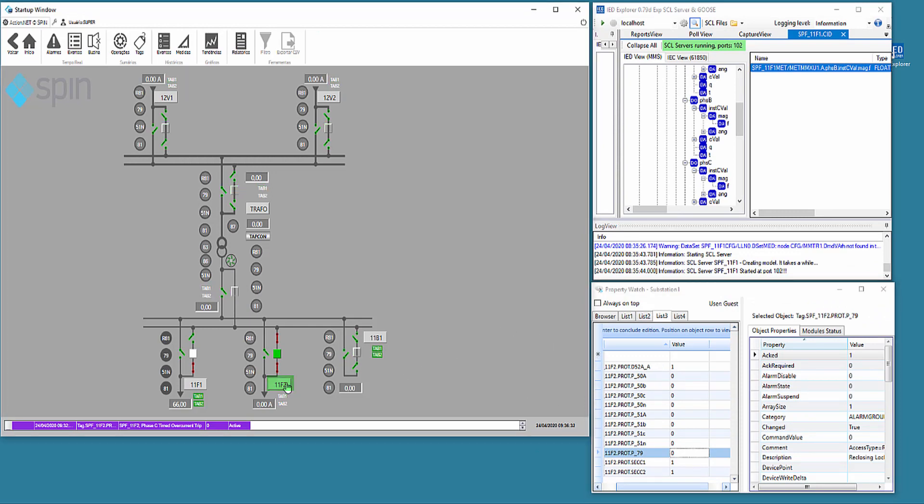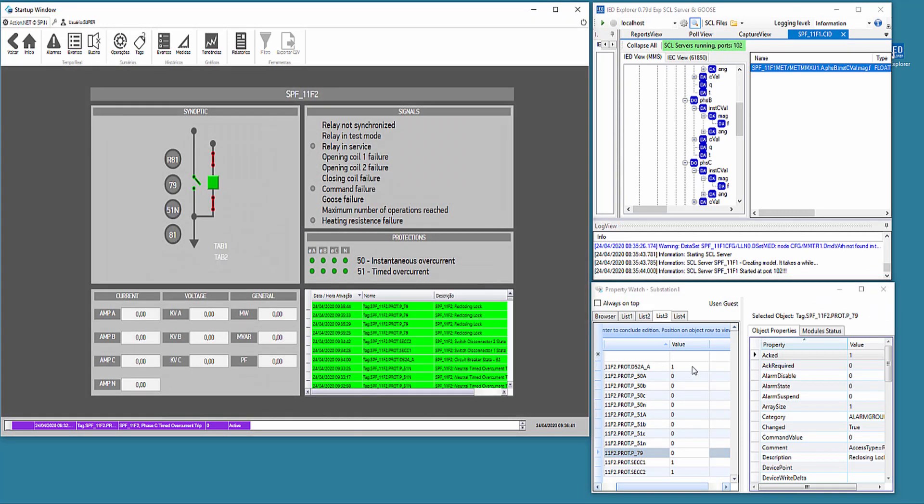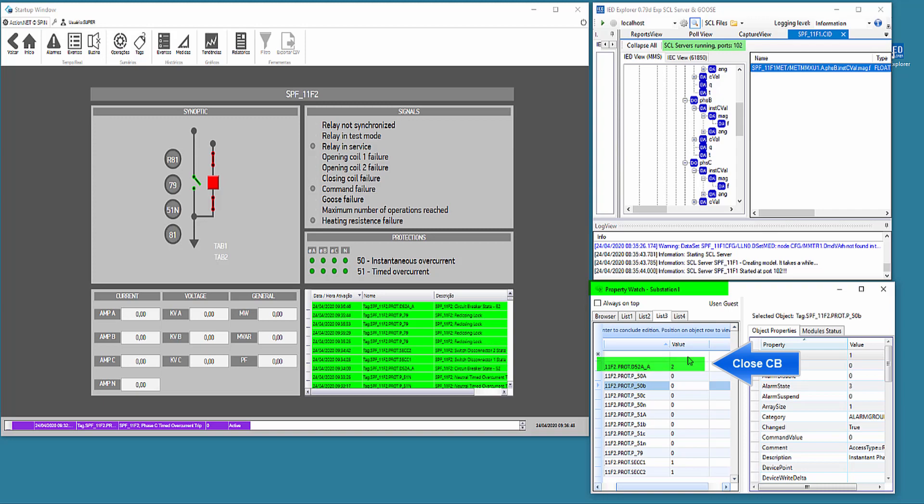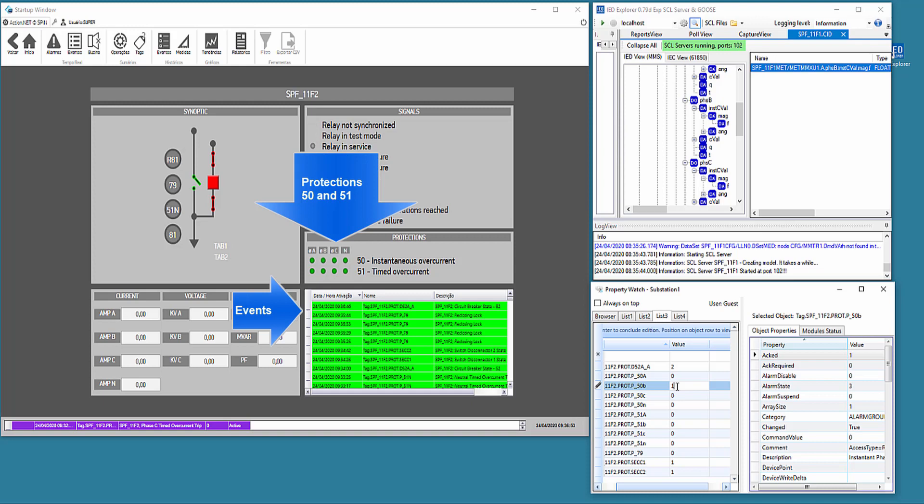We will navigate to the detail of feeder 11F2, and using the property watch tool, we will simulate some changes showing its usefulness to test the behavior of the application. We close the circuit breaker and act on instantaneous and temporized overcurrent protection, seeing its changes.